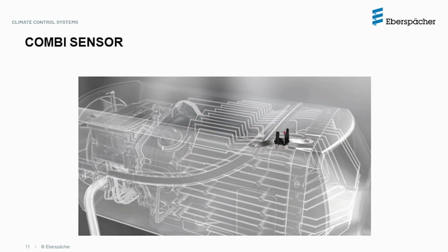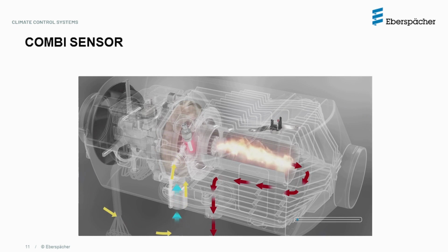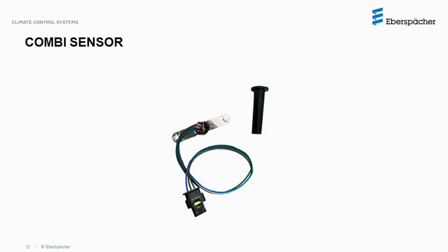The combination sensor assembly has been redesigned. It is installed on 2 posts that are part of the heat exchanger casting and is locked in place securely by folding the tabs on the mounting strap of the combination sensor. The combination sensor assembly has the same function as before. The flame sensor will detect the temperature rise of the heat exchanger, and the overheat sensor will serve as overheat protection. A special plastic tool is included with every spare part to bend the locking tabs to the correct angle and securely hold it in place.